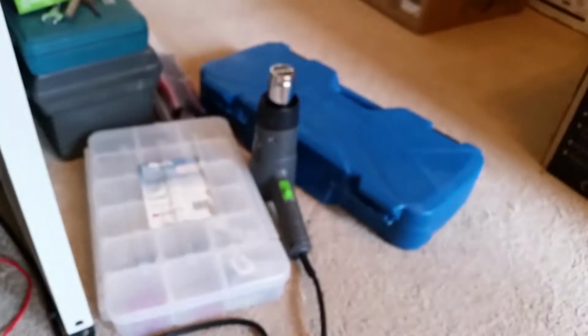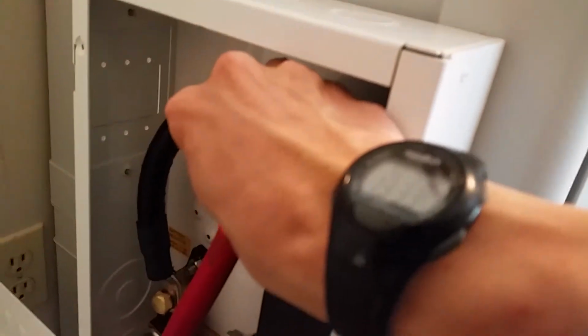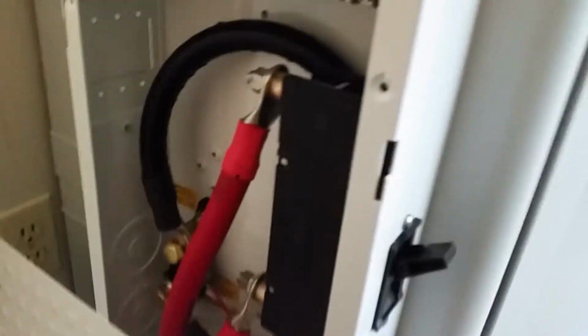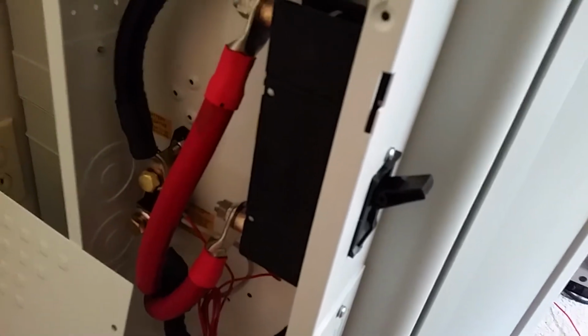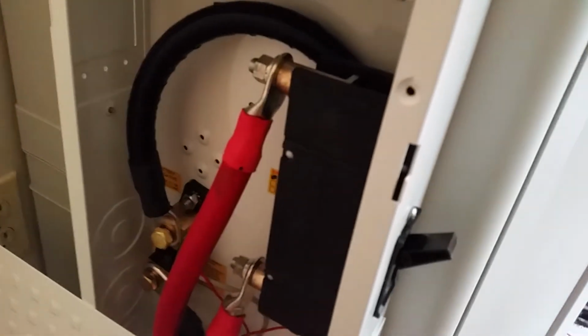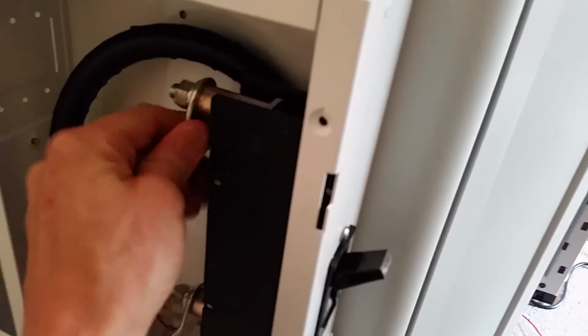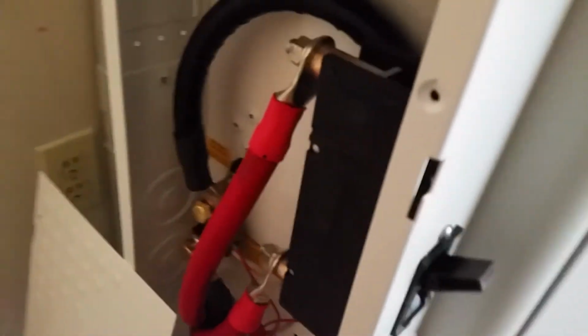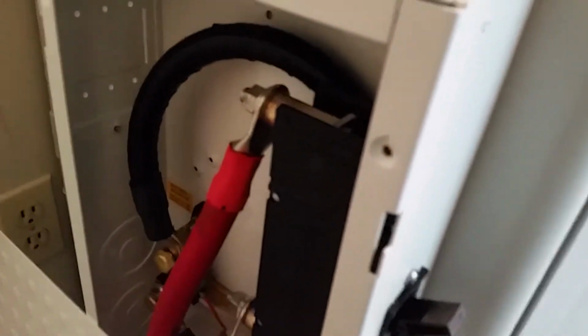So I've been doing some checking over the system here. I haven't changed the load, it's still on, heat gun still on low. Even these 4-aught gauge wires are getting warm over here for some reason. I'm a little surprised, but maybe it's not that big of a deal because it's a 12 volt system versus the 24 volt one I have downstairs, so there's more voltage drop going on in this system. But they're around 85 degrees Fahrenheit, something like that—just warm, not too bad, but kind of interesting.